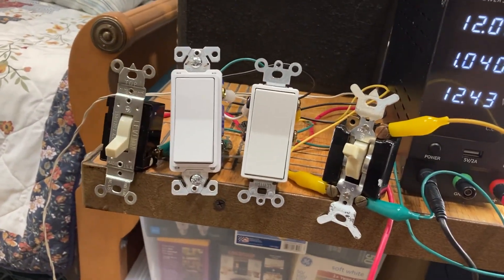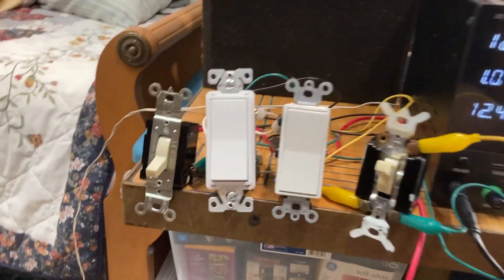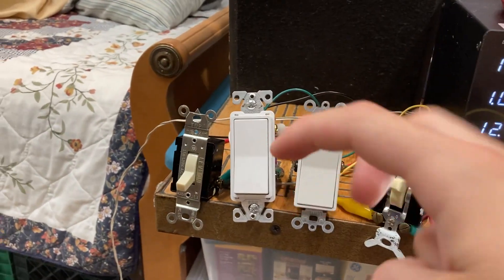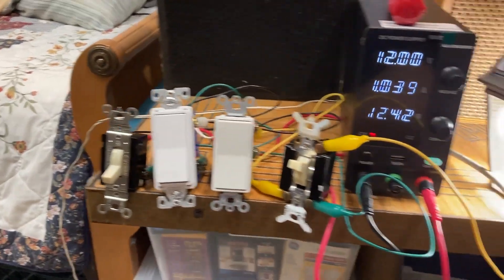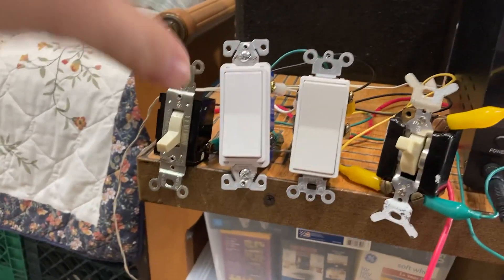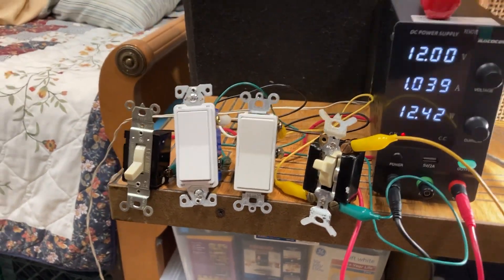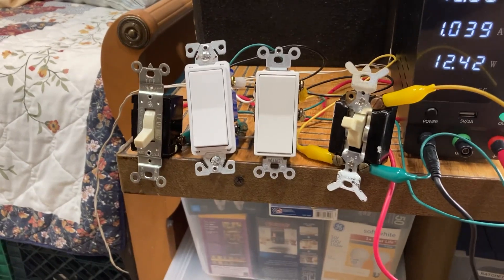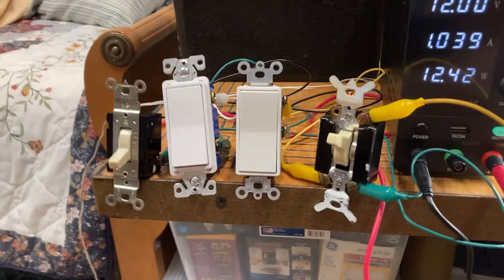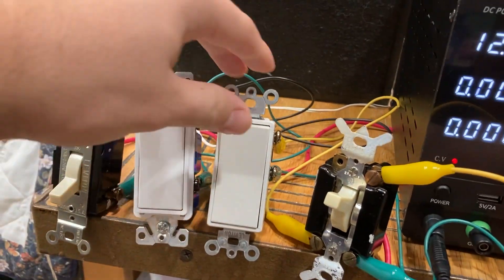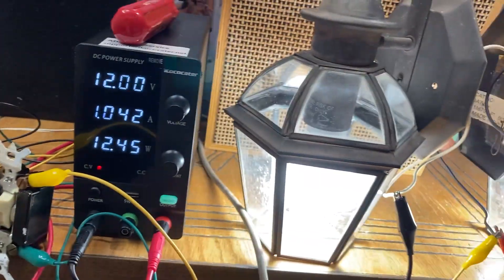A lot of people get terrified of these four-way switches, but they're really not that difficult. You just got to know which one's your power coming in and which one's going out to the load or your lights or whatever. You can hook as many of these four-ways up as you wanted to. If you wanted to put 10 of these in, you only need two three-way switches and eight four-ways. Just like that, just like that.